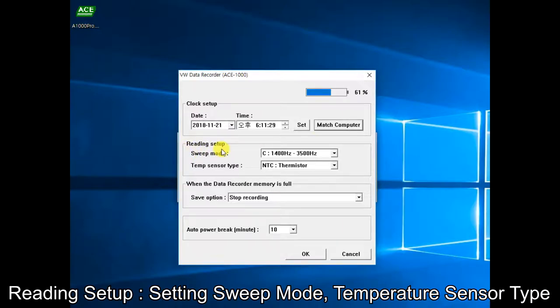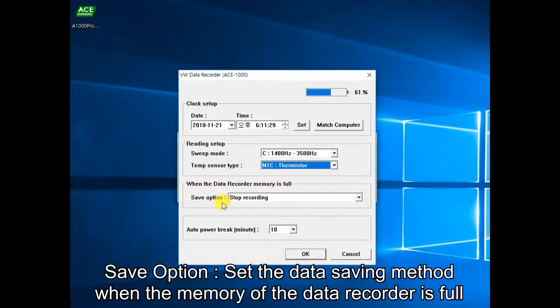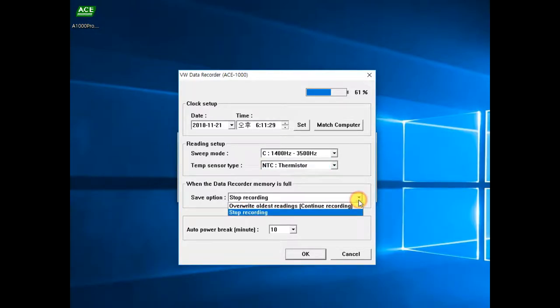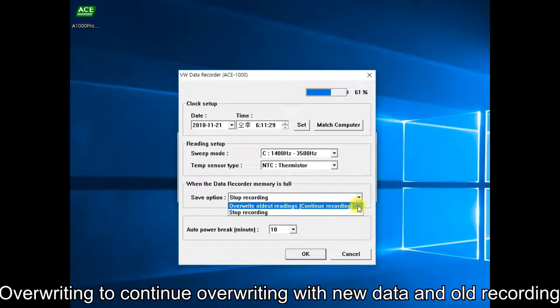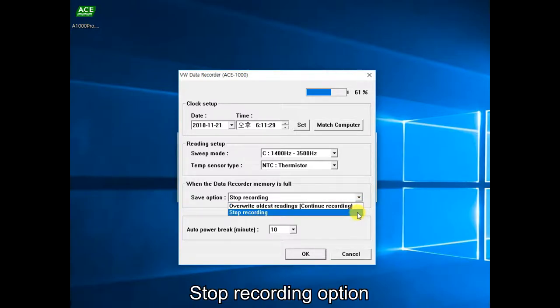Reading setup is the function to set the sweep mode and temperature sensor type. Four sweep modes and two temperature sensor types can be configured. The save option sets the storage mode when the device memory is full. The first mode, 'continue recording,' saves the most recent data by erasing old data. The second mode, 'stop recording,' stops storing new data when the memory is full.